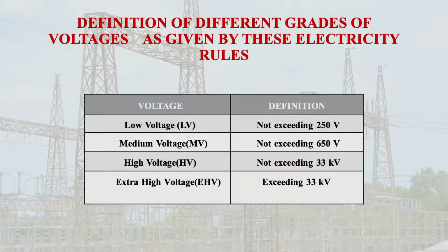We first state the definitions of the different grades of voltage as given in these rules. What are these voltage limits or grades? They are low voltage, medium voltage, high voltage, and extra high voltage. Low voltage means a voltage not exceeding 250 volts. Medium voltage means a voltage not exceeding 650 volts, that means between 250 and 650 volts. High voltage is a voltage not exceeding 33 kV, that means between 650 volts and 33 kilovolts. Extra high voltage is a voltage above 33 kilovolts, the voltage exceeding 33 kilovolts.